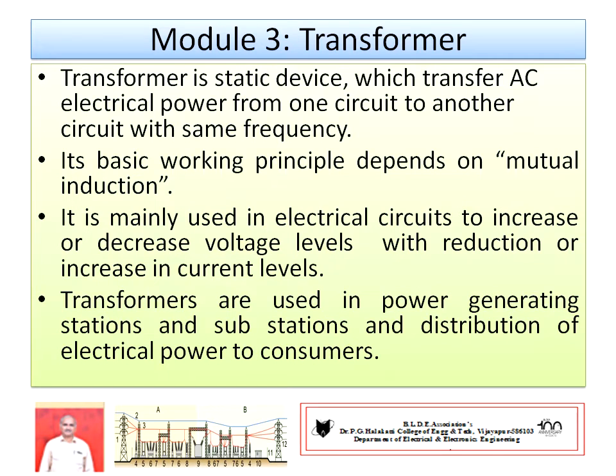For example, it is mainly used in distribution of electricity to the consumers, that is known as distribution transformer. Every house connection is taken from poles, which are connected to the distribution transformer. Its main function is to reduce the voltage level from 11 kV to 440 volts for three phase consumers or 230 volts for single phase users.